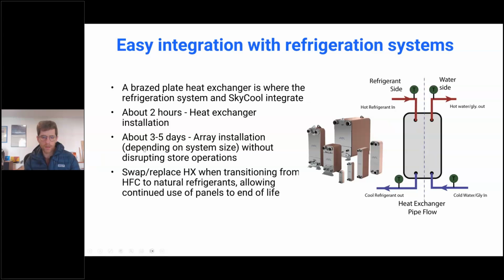Generally, we're interfacing the system with heat exchangers. So we use brazed plate heat exchangers. These are relatively common in cooling systems, but in terms of the installation of the heat exchanger, it takes, you know, around 2 hours. A lot of the prep work is done before cutting in, and then it's just essentially brazing in the pipe.